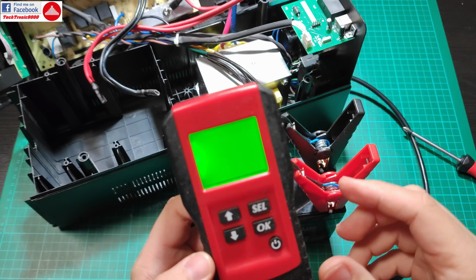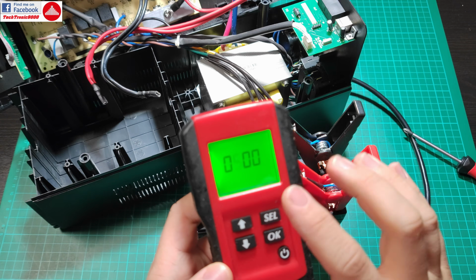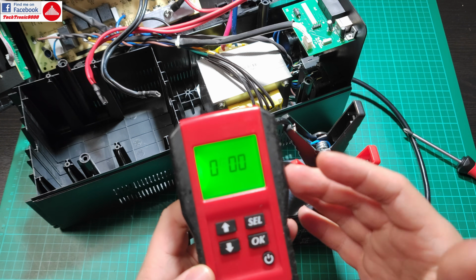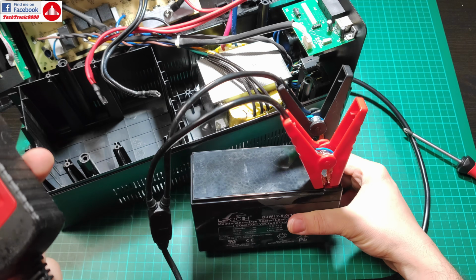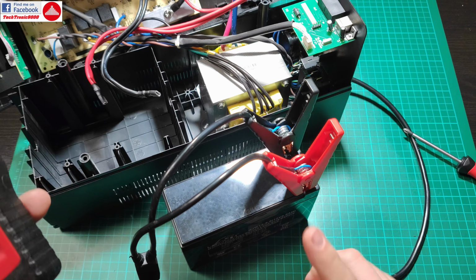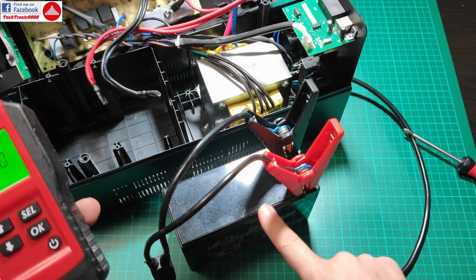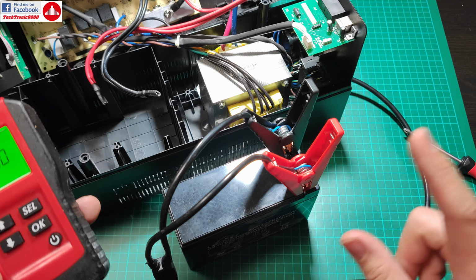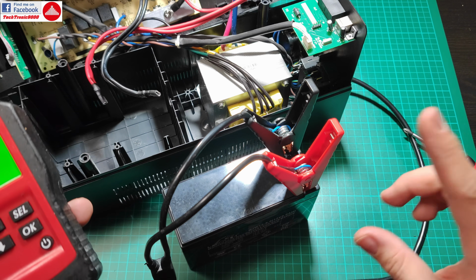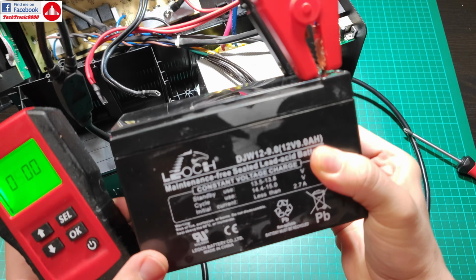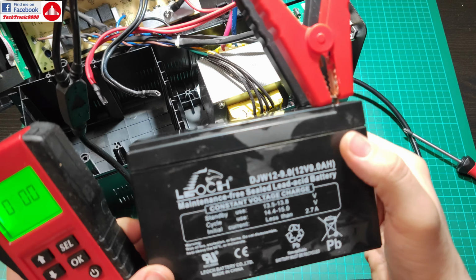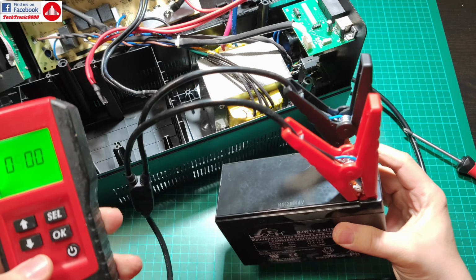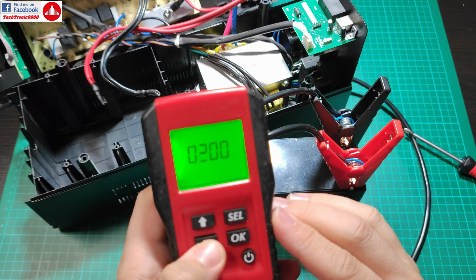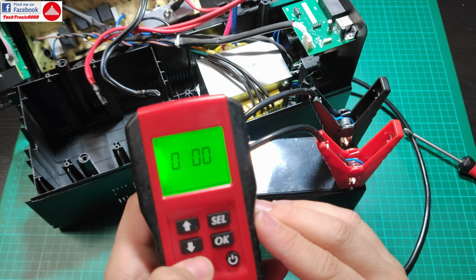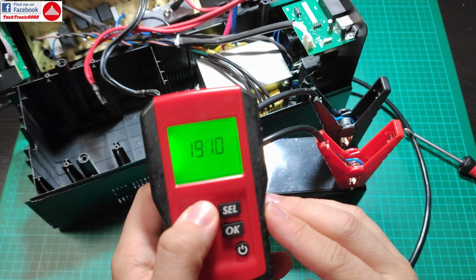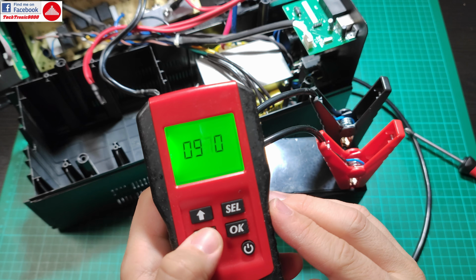Now I'm going to power this on, and it does a self-test, and now it asks me for CCA, cold cranking amps. This isn't a cranking battery, but for reference, a 7 amp-hour sealed lead acid battery usually has something like 80 to 120 cold cranking amps capacity. This is a 9 amp-hour battery, so it should have a bit more than 100 amps. Just to be safe, I'm going to set this at the minimum of 80 amps capacity.